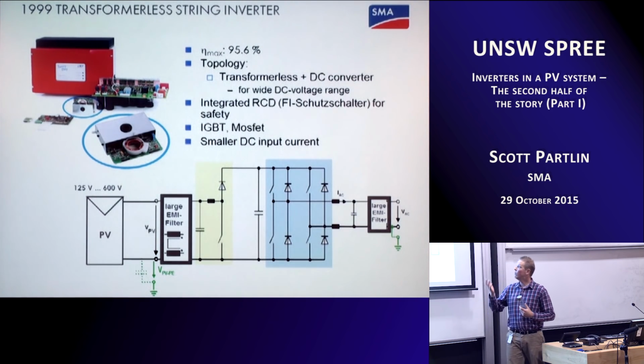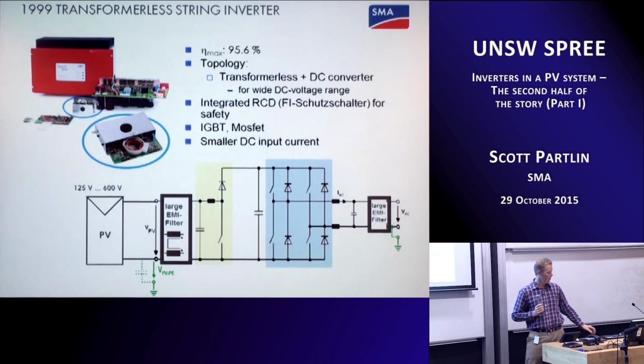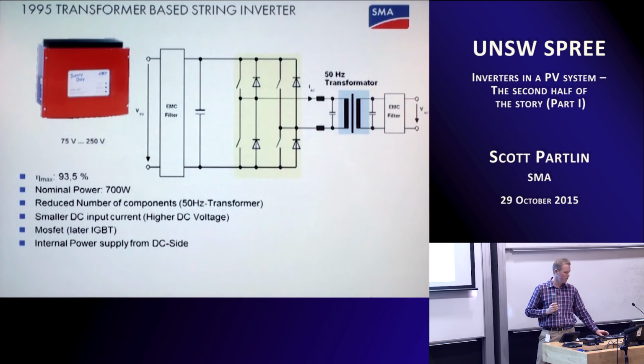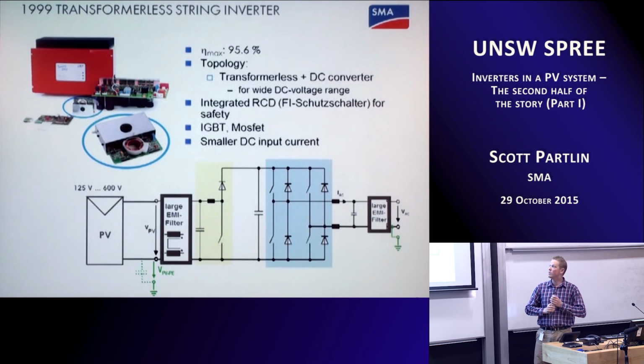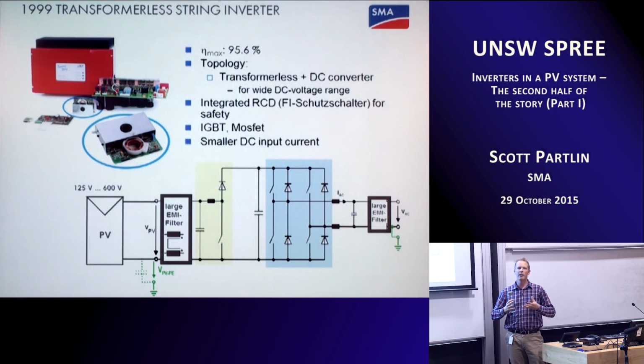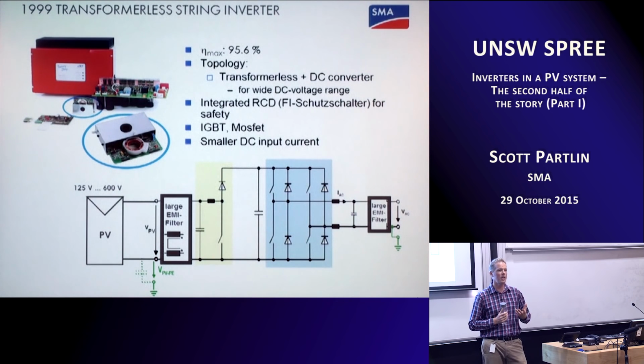We're looking at an inverter here that was slightly higher power, about a kilowatt compared to the previous 700 watt inverter. Whereas here we've got something that weighed about 25 kilos, here we've got something that weighs about 16 kilos. So part of the improvement in the technology over time is not just the efficiency improvements in going from transformer-based to transformerless, but also a reduction in component numbers.